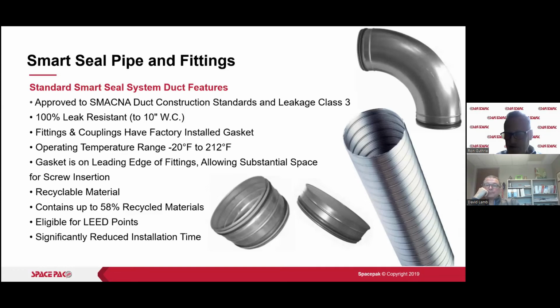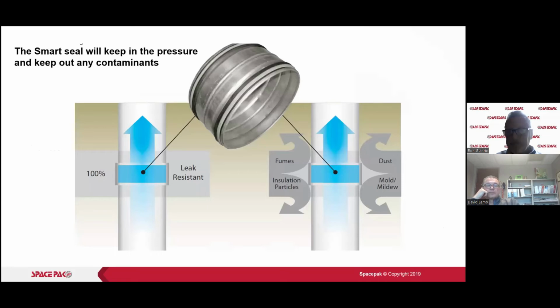Smart seal pipe fittings. We talked about that. Gasketed spiral, up to 10 inches water column, leak resistance. It's hard to get them apart once you put them together. All right, so this is really what you should use here. It comes with insulation as well. You'd have to buy that separately with standard galvanized pipe anyway. All right, completely leak resistant.